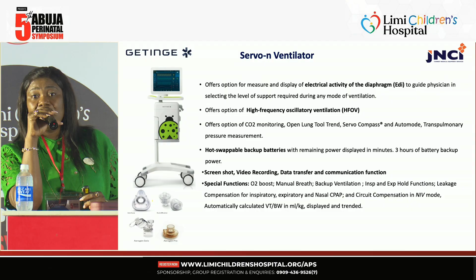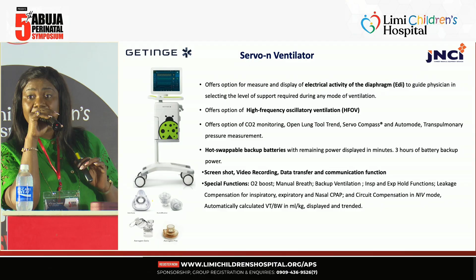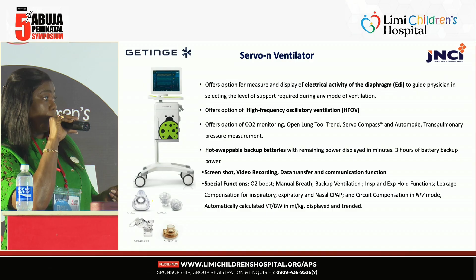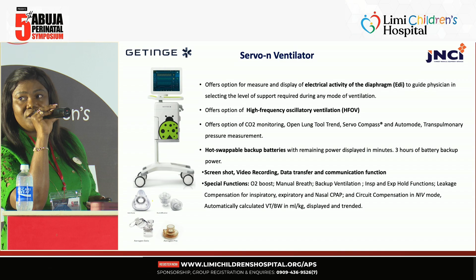Now, this is a plus for the ventilator because it has a support mode, a 3-hour capacity battery, and it comes with 2 battery slots. Which means you have 6 hours of battery capacity. And you can change the batteries even while the ventilator is working, and it does not stop ventilation. Ventilation continues while you are doing a battery change. And other special functions like calculation of tidal volume based on baby's body weight and the capacity to do a circuit compensation. So it does a circuit compensation when the circuit is automatically attached to it.